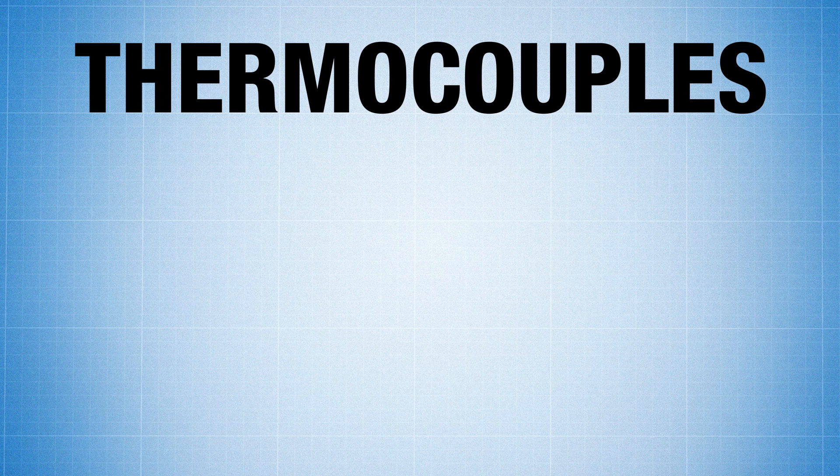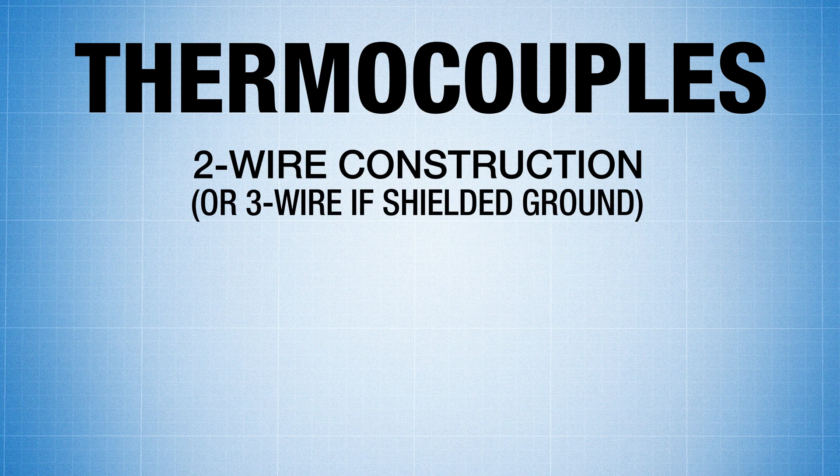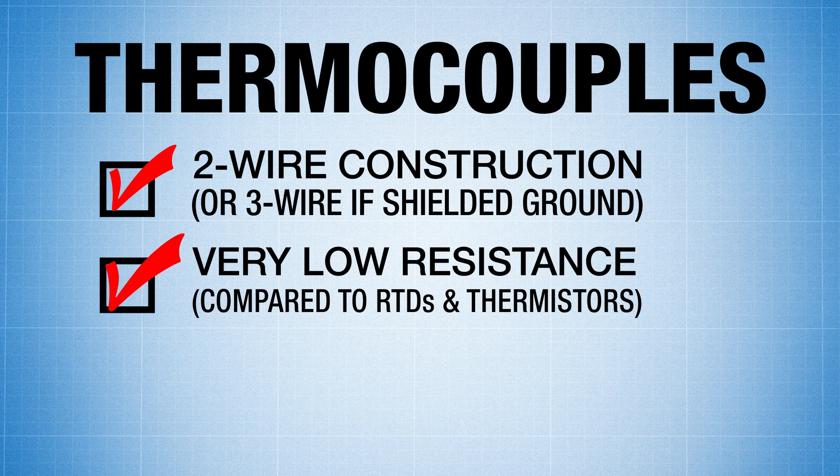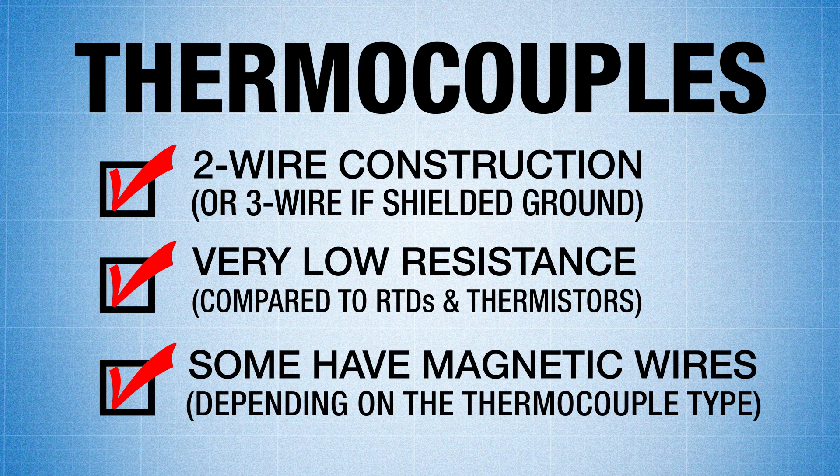First, let's look at thermocouples. They usually come in a two-wire construction or a three-wire if there's a ground or shielding wire. They have a very low resistance compared to RTDs and thermistors. And some wires can actually be magnetic depending on the type of TC.